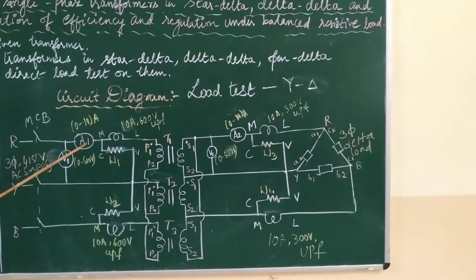We have three phase AC supply RYB. So in the primary we have an ammeter connected here to measure the current, and then it is connected to the wattmeter. Along the R line it is connected to wattmeter. Through wattmeter it is getting connected to P1. We can observe here that P2 of first transformer, second transformer and third transformer are connected in series. They are shorted together, because it is star connection, and P1 of all the three transformers are connected to the supply.